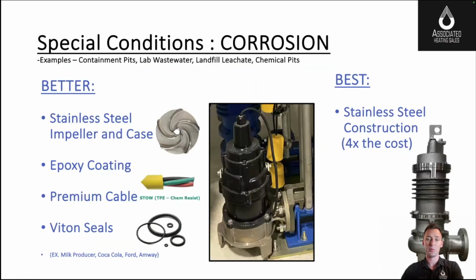Corrosion. If you have fluid present in your pit that's corrosive, you have some options. When I look at what's happened over the last 10 years as far as corrosion-proof or resistant pumps, there's two different categories of customers. The all stainless steel pump, which you see over here, we sell a few a year. They're very expensive. They're 4 times the cost, as we mentioned. They work really well. They're rated up to that 200 degrees. They'll be in there a long time.